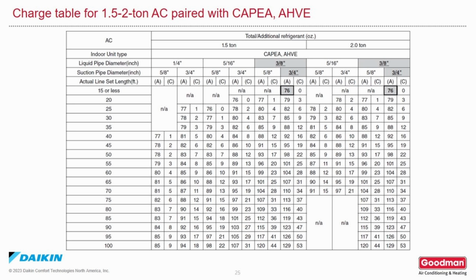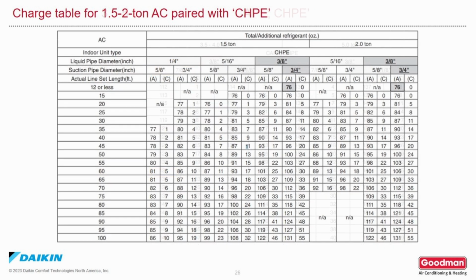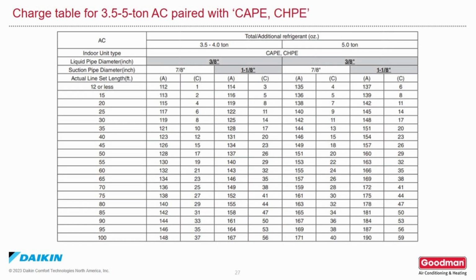Here are some examples of the charge tables in the installation manual. Notice that each one shows the line set diameter, and there's an A column and a C column. The A column is the total charge. The C column is the additional charge that you would add. So in this case, if we had a 1/4 and 5/8 line set, and the line set was 60 feet long, the total charge is 80 ounces. The additional charge that we would have to add is 4 ounces. Make certain that you have the correct charge table for the unit you're working on. Here are a couple other examples of different size unit charge tables.